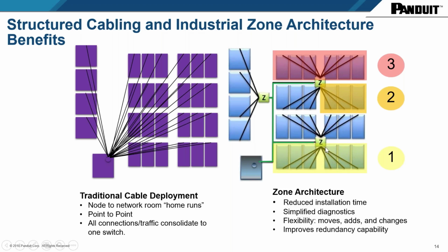If a certain cable is broken inside of a cell, you're affecting just the one area in the cell. You will not be shutting down all of these different areas to run a cable from the central system to the affected zone. So these are ways of running a network inside of a factory where you have to really consider the MICE rating, where you have to really consider the architecture, where you try to optimize the cost of your cabling and connectivity.